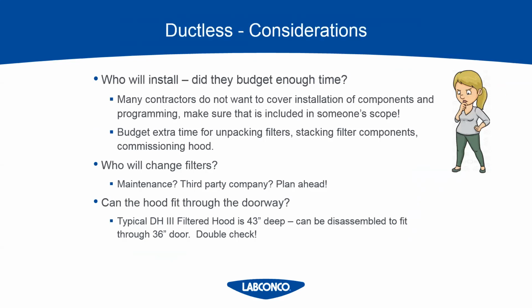Can the hood fit through the doorway? This applies to both your ducted and ductless, but I did want to focus here on the typical DH3 filtered hood. It has that control box on the front, and it's 43 inches deep. It can be disassembled to fit, but once again, in terms of installation and labor, you have to plan for disassembly to put it in the room. So just keep in mind your doorways. Where does the hood have to go in order to actually get to your lab to be installed?